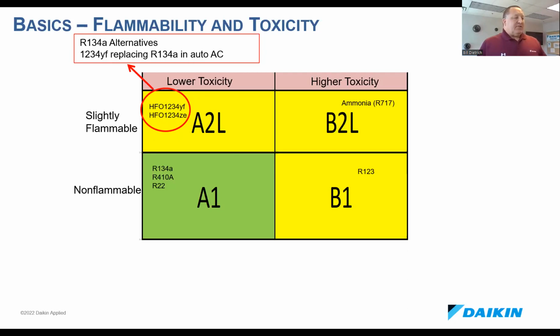So what that means is, to use ZE effectively, you're going to have to redesign compressors to maybe make an impeller bigger, make a screw longer, that type of thing, to pick up that extra CFM and recover that capacity. But long term, you'll see both of these refrigerants used quite a bit.